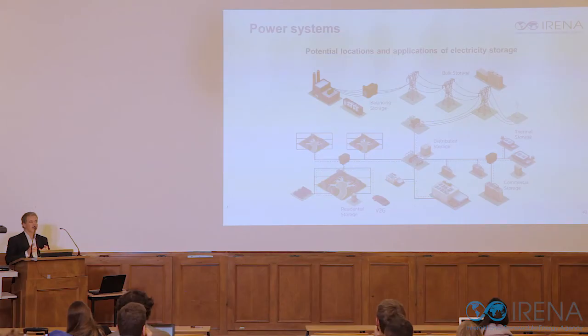different timescales. So electricity storage, like solar PV, is very modular. You can put it in a lot of different places in the energy system. You can put it behind the meter, pair it with your rooftop solar PV. A distribution company can put it at its substation to delay investment upgrades. If new suburbs are being added, transformers might need to be upgraded, you can put in distributed storage to delay that investment until you have a nice economic chunk of transformer capacity you could add that's going to be utilised, not having a large capacity underutilised for 5 years until the suburb comes online.